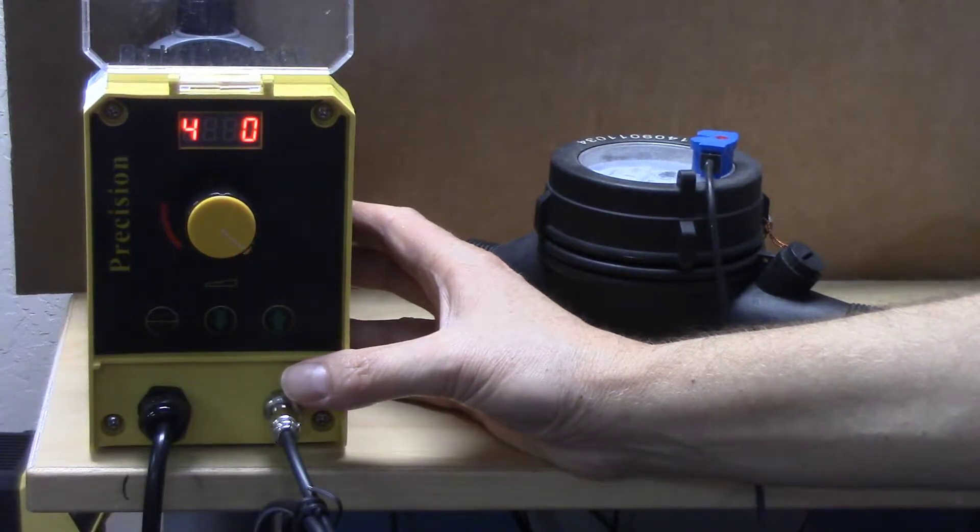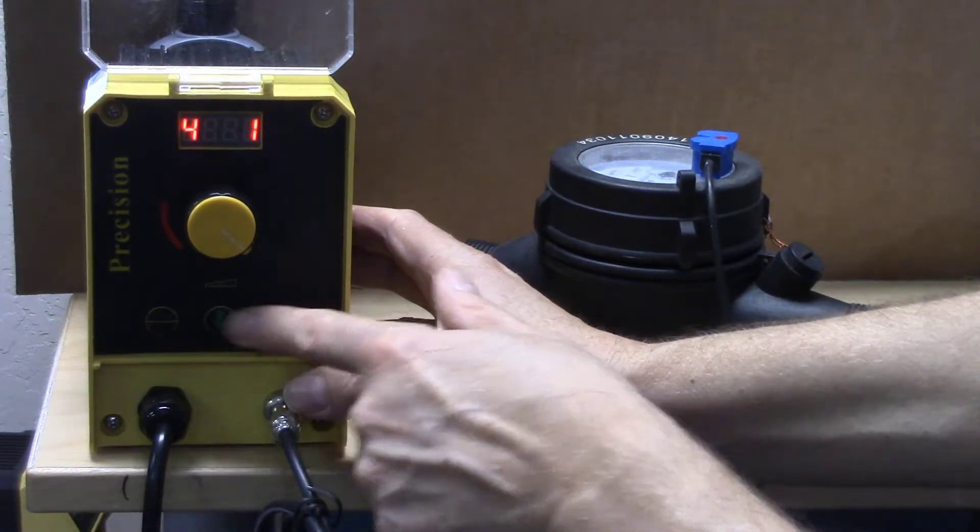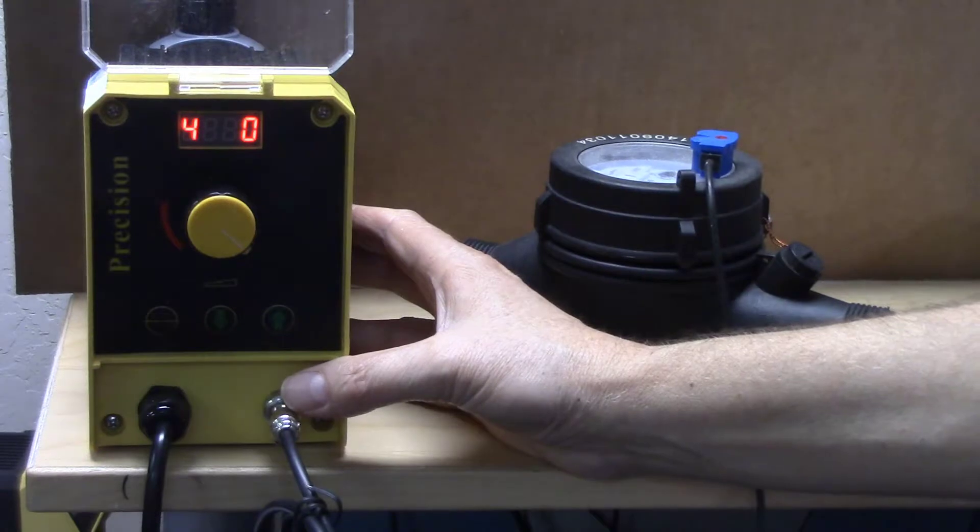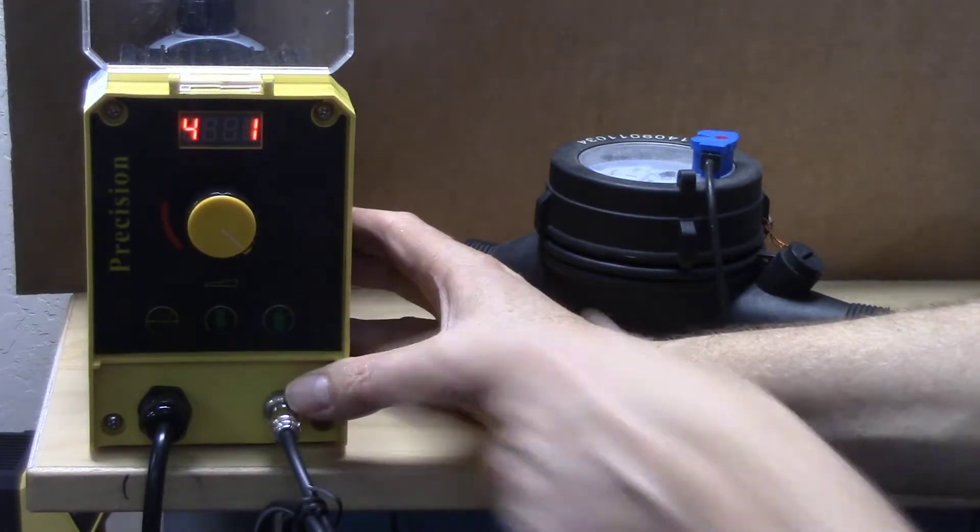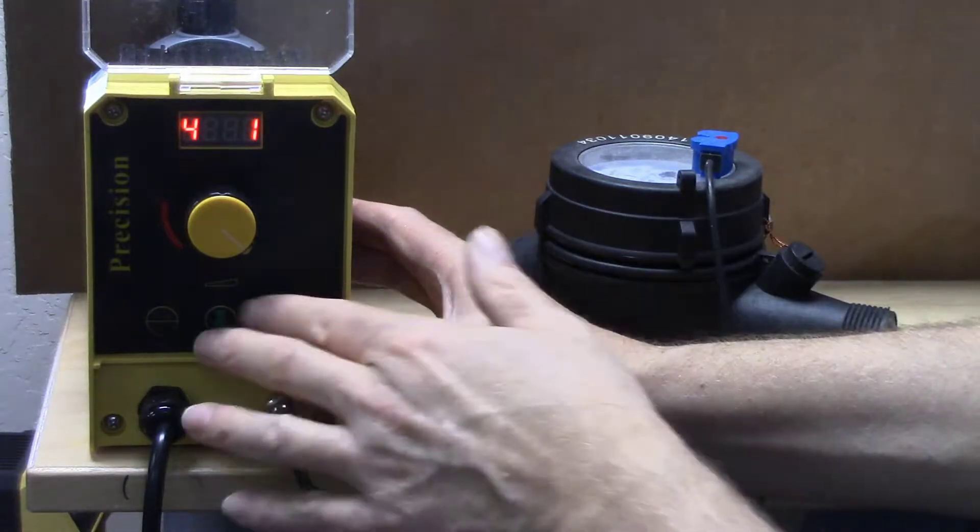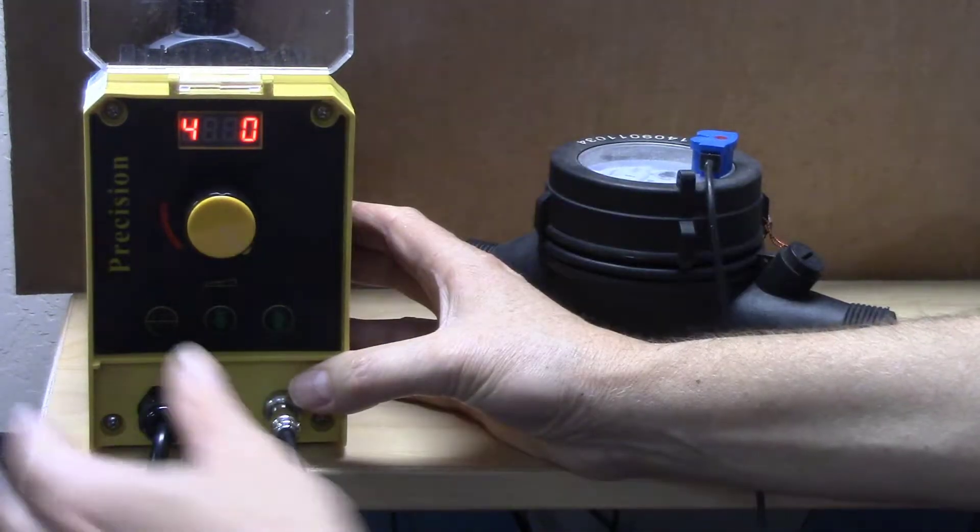Parameter four, the last programming parameter, only has two states: zero and one. It must be on zero. If your pump isn't pumping, go to parameter four and make sure it's on zero. If it's on one, it means it's waiting for an external control input, which we don't have.